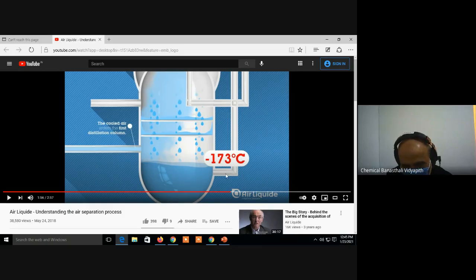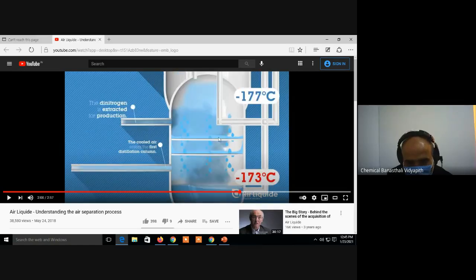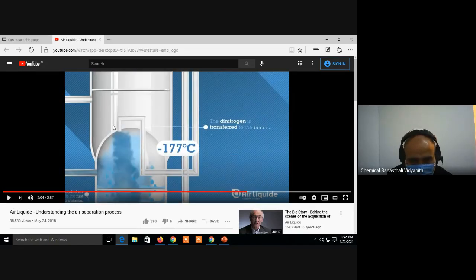Now look at the temperature here. This is a cold liquid phase, at minus 173, and the nitrogen coming from the top is at minus 177 degrees Celsius. So when this nitrogen comes into contact with this heat exchanger, try to understand, this is just a heat exchanger. We are not mixing two streams, it is just exchanging heat. So this vapor phase nitrogen will come in contact with this liquid phase oxygen. What will happen? Nitrogen will cool down and oxygen temperature will rise. So oxygen and argon will rise from this tube and nitrogen will rise from this tube.